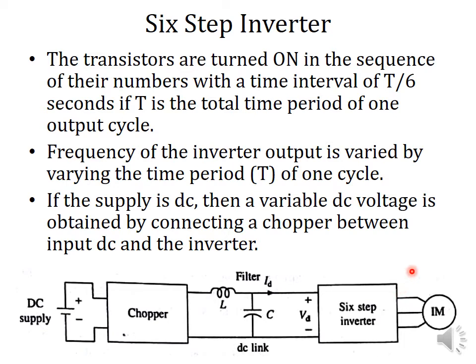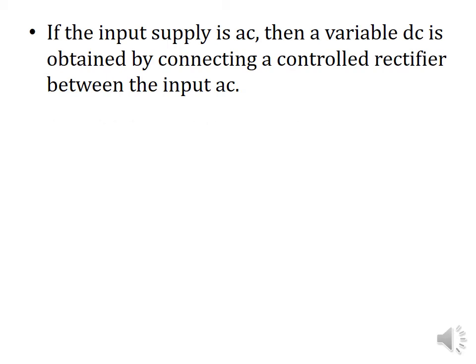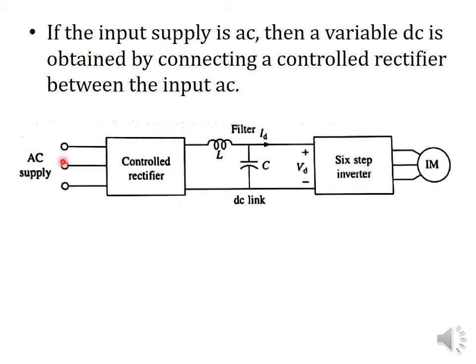If the supply voltage is AC, instead of using a chopper we can use a controlled rectifier. Here, a three-phase AC supply is used with a three-phase fully controlled rectifier. Its output voltage is given to the six-step inverter, which supplies the induction motor. The induction motor is then controlled by V/F control.